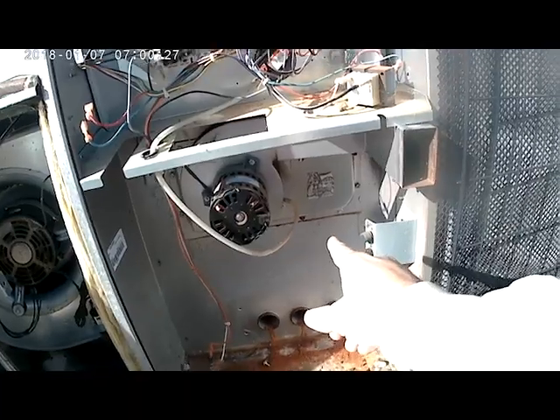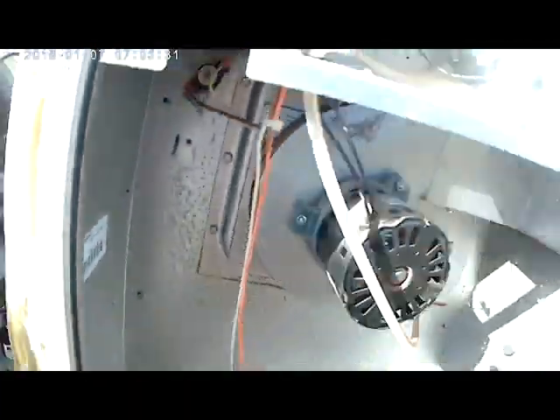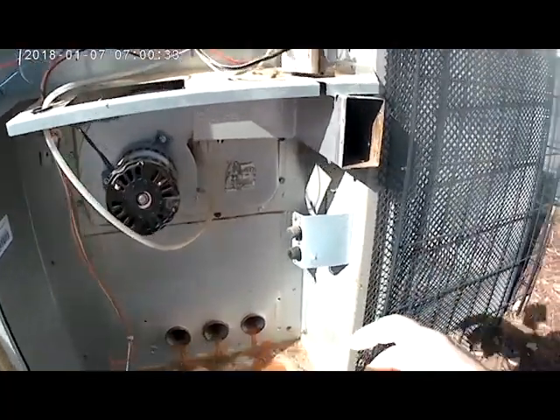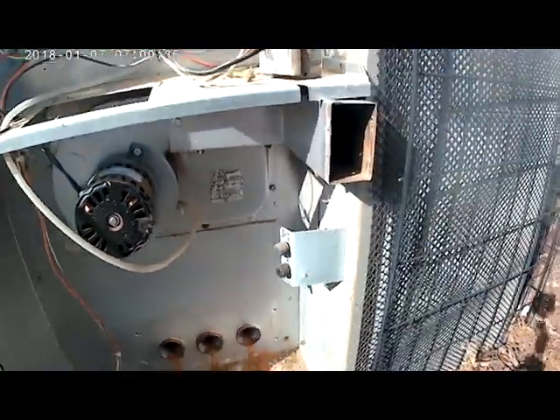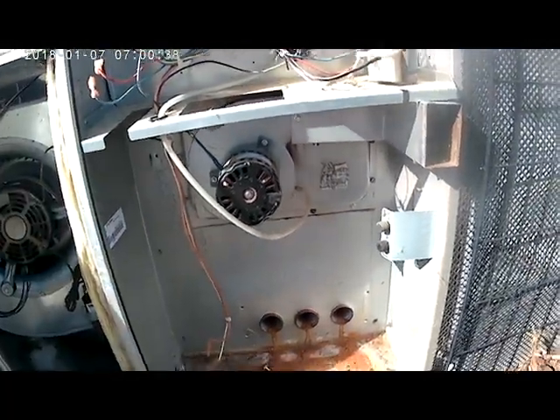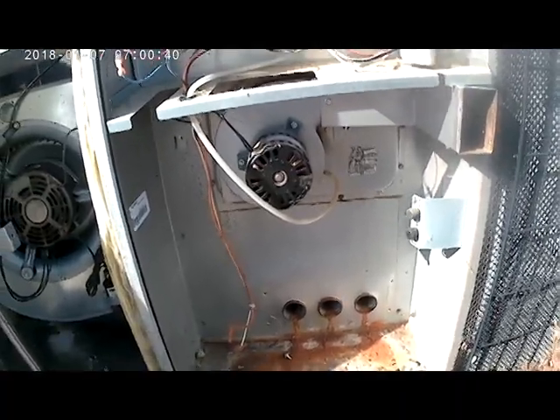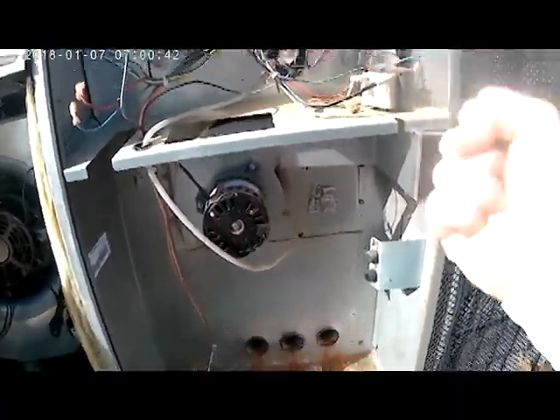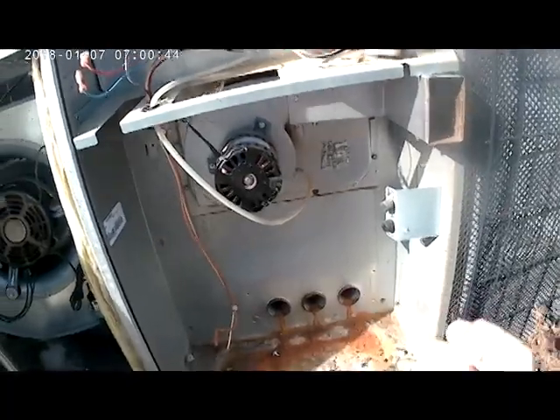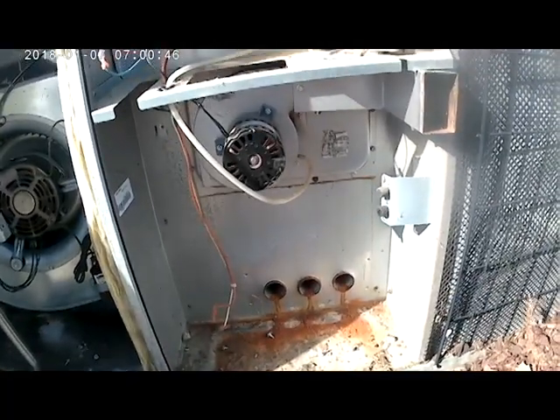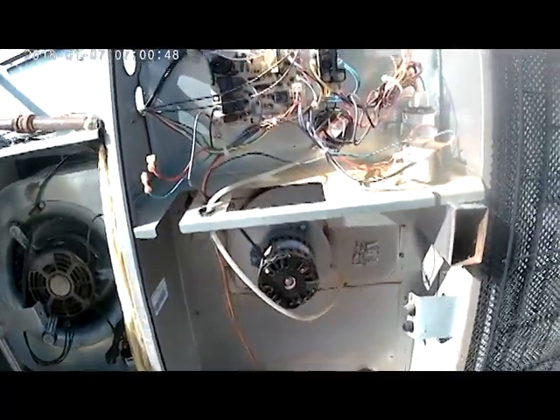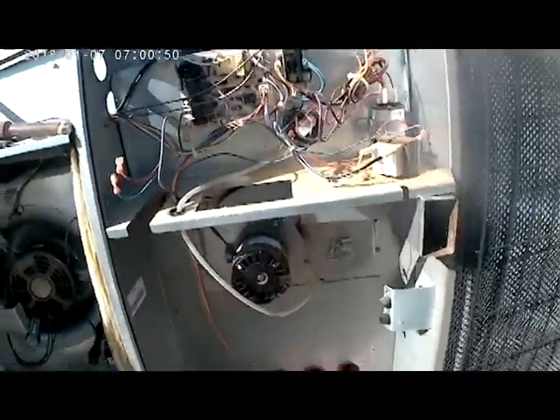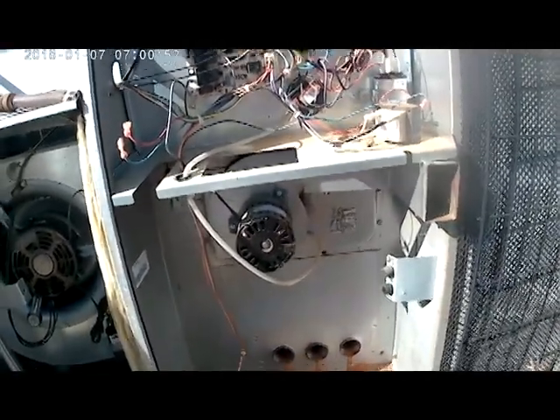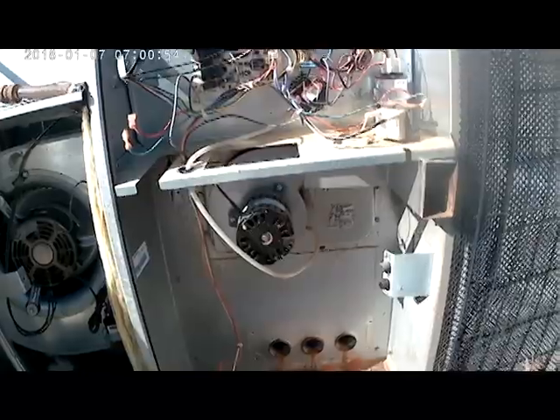We're going to have to take the inducer motor assembly off, and remove that limit switch up there. If I'm right, we're going to have to take this out and slide it back through. Once we get all the screws out, we can wiggle it loose and pull it straight out of this furnace. So I'm going to start working on getting the inducer motor out and see if we can get this heat exchanger loose.